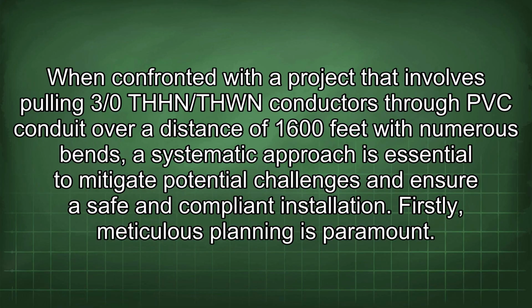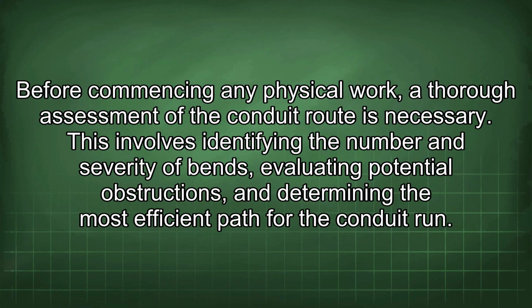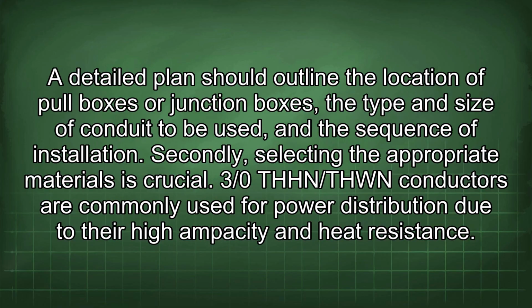Firstly, meticulous planning is paramount. Before commencing any physical work, a thorough assessment of the conduit route is necessary. This involves identifying the number and severity of bends, evaluating potential obstructions, and determining the most efficient path for the conduit run. A detailed plan should outline the location of pull boxes or junction boxes, the type and size of conduit to be used, and the sequence of installation.